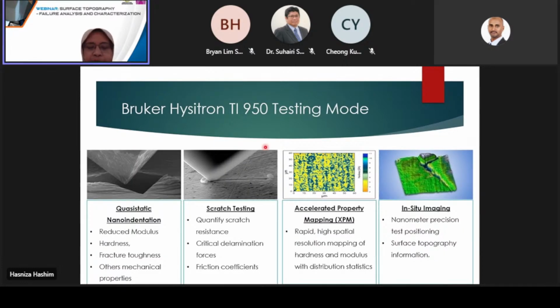These are the main modes available on our Bruker TI-950 tester. We have quasi-static nano indentation, which most people just refer to as nano indentation. The properties most commonly measured through nano indentation are elastic modulus and hardness. However, the technique can also be used to extract other information like fracture toughness or other mechanical properties. There is also a scratch testing mode, which can be used to determine properties like the coefficient of friction or adhesion properties of a film on a substrate, if you have failures like delaminations.